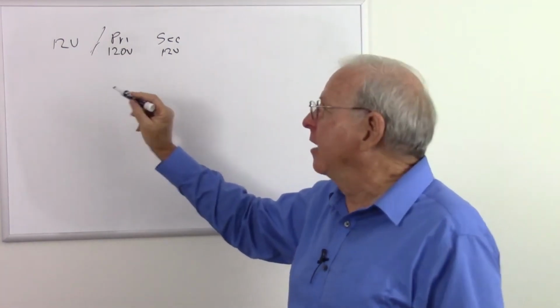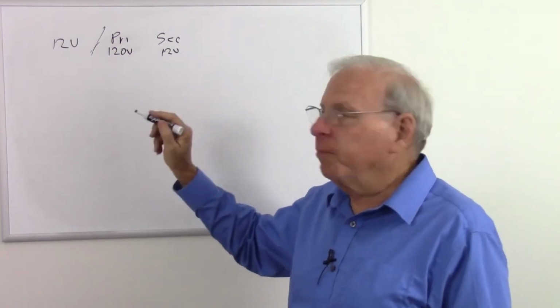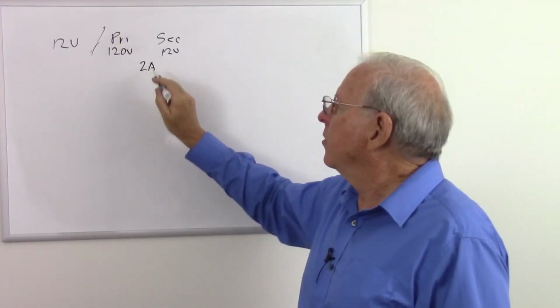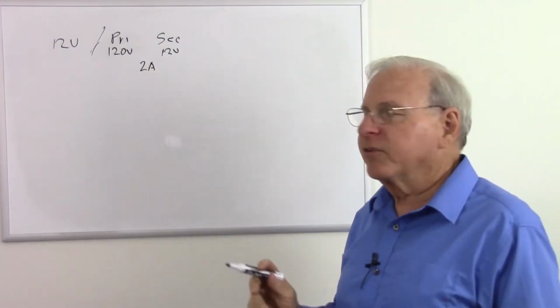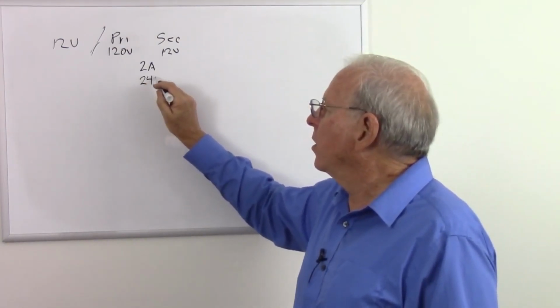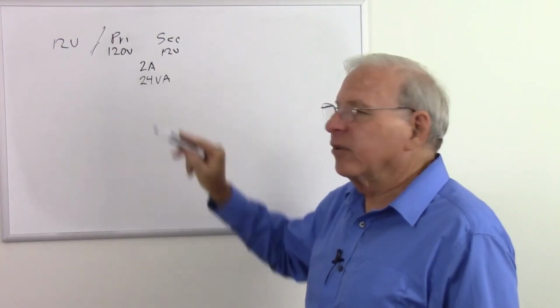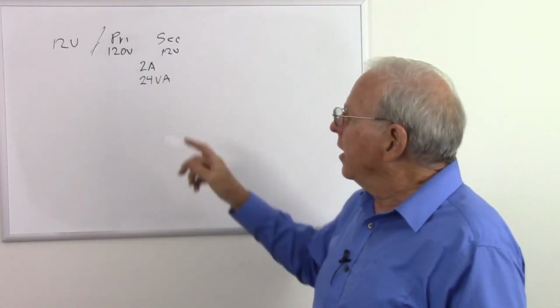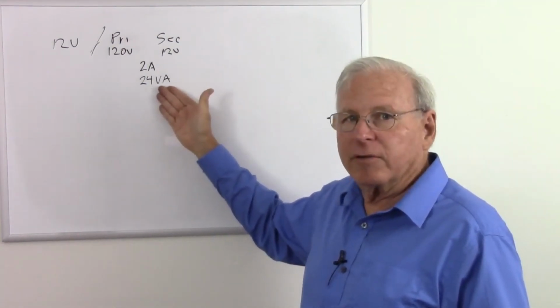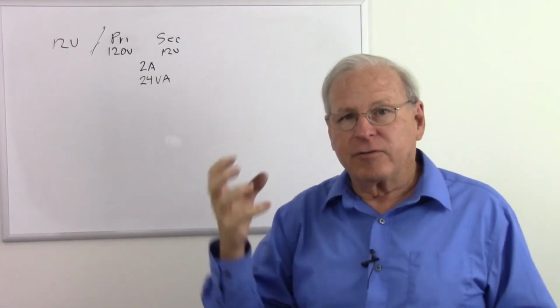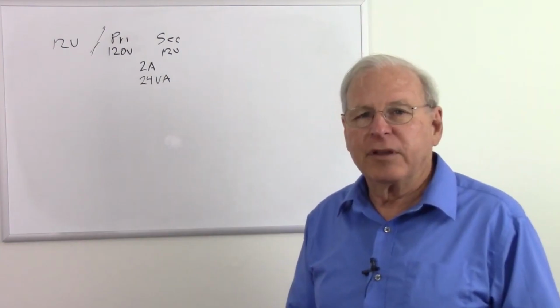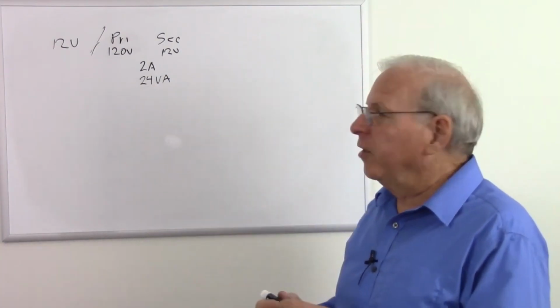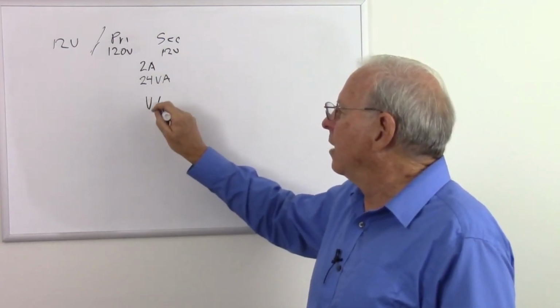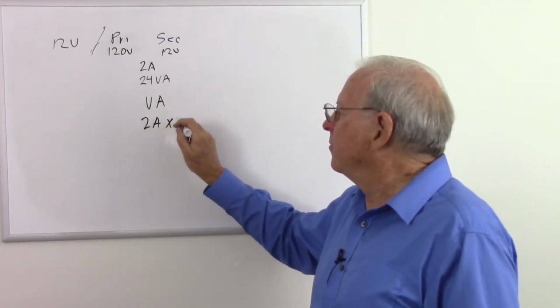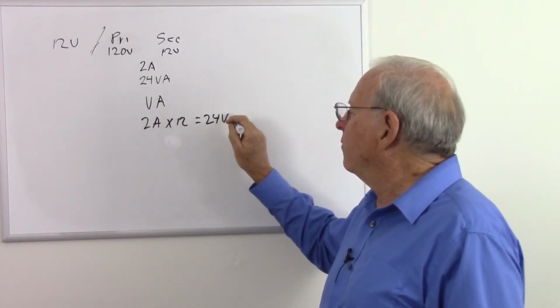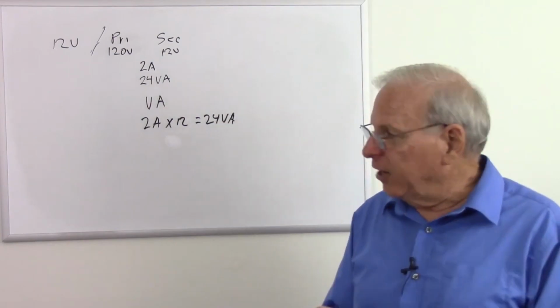And then as far as how much current it handles, sometimes they specify it as a particular output current. Let's say 2 amps. So it says the secondary can handle 2 amps, or it might say 24 VA. 24 VA is the same as 2 amps. So you have to kind of figure that out. If I want to have a certain amount of current in my secondary, and my transformer says, oh, you have a 24 volt amp transformer, I have to calculate that out, knowing that, of course, my volt amps is going to be volts times amps. So I take my 2 amps times 12, gives me 24 volt amps.